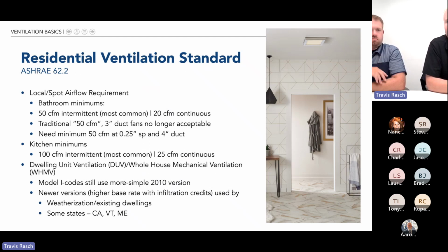I won't hit all the bullets here, but there are 2 key pieces of ASHRAE 62.2. One, in terms of local or spot ventilation, in bathrooms you need 50 CFM delivered at the end of the day, and in kitchens you need 100 CFM exhausted out of the kitchen. You need to have that capability once the product's all installed. Probably more importantly, the major bullet at the bottom is dwelling unit ventilation. You'll hear it referred to as DUV. Other people call it whole house mechanical ventilation.